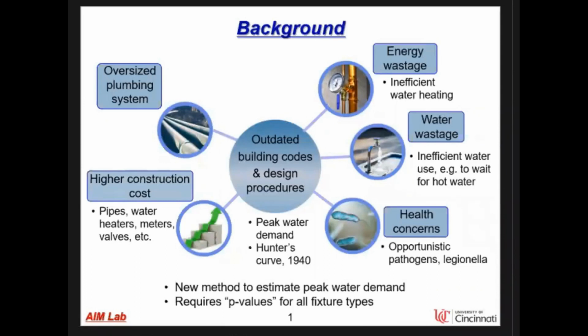A new method to provide greatly improved estimates of peak water demand has been recently developed and adopted in the National Uniform Plumbing Code in the US. However, it requires a critical piece of missing information on the probability, or the p-value, of fixture use during peak hours for all fixture types in a specific type of building.